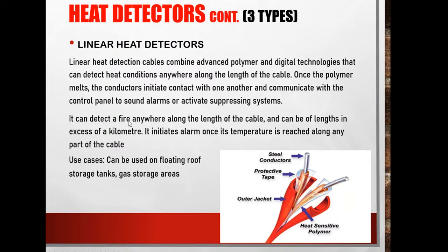So it can detect a fire anywhere along the length of the cable, and can be in excess of a kilometer. It initiates alarms once its temperature is reached along any part of the cable. So an alarm will go off once that set temperature has been reached anywhere on the length of the cable. It's very useful, especially in floating roof storage tanks, those large tank farms you see. Then in gas storage areas.